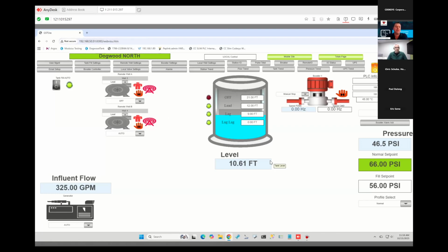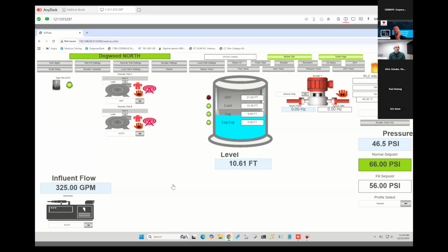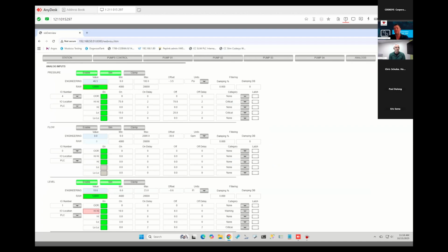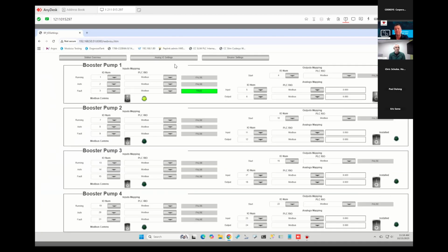So this is, for you CODESYS guys out there, the actual web visu we're hosting from one of our appliances. What's unique is, from the operator standpoint, as long as he dials into the local IP address here with that web visu, he's able to get into the controller and from here do everything as far as setup is concerned. So the first thing I mentioned, which was nice, is being able to configure where these I/O signals are going. So for retrofits, you might have VFDs that are over Modbus. So you can see here with our drop downs in CODESYS, I can scroll down and pick Modbus and control over Modbus. Or I can pick any of the remote I/O modules I might have installed, or my actual PLC, which would be the base PLC appliance there in the field. So this allows me to map everything to do with that PLC, with that device.